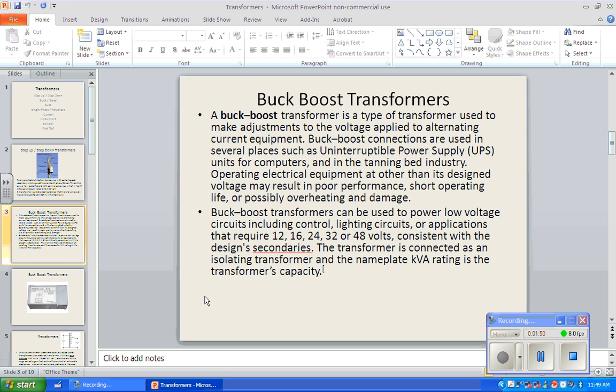Buck boost transformers are generally used for special purpose. They're still step up, step down, sort of. They're not. Because a step up or a step down is where you're changing the voltage a lot. You're going from 480, 277, 480 down to 120, 208, which is like a 2-to-1 ratio, or a 4-to-1 ratio, or a 10-to-1 ratio, something like that. You're stepping up or down a lot with a step up or step down. With a buck boost, you are making a very minimal change.